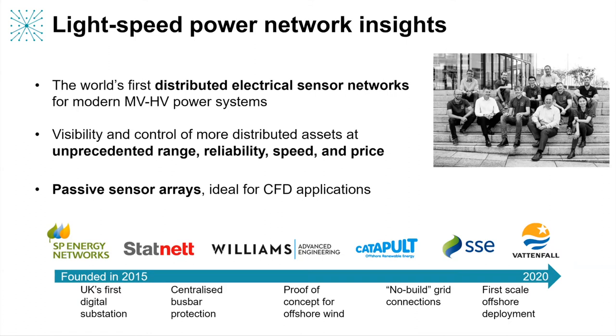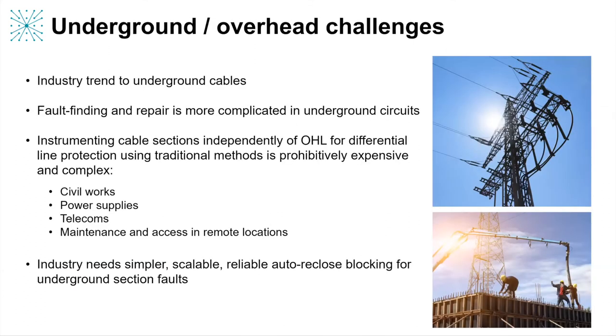There are clearly a lot of different novel applications that these sensors can be used for, but one immediate, simple and very clear application is in cable protection or cable fault detection — CFD — so that's what we'll be focusing on today. Just to begin with, why would we need a CFD solution? There is a general industry trend to underground cables, whether this be for urban areas or to protect areas of natural beauty in the countryside, and there is a corresponding increase in the numbers of hybrid circuits in transmission and distribution operation networks.